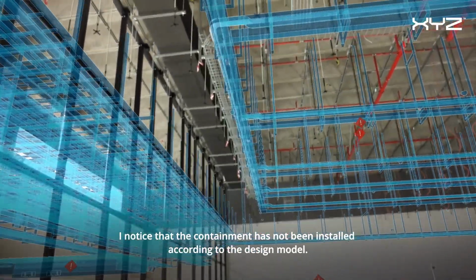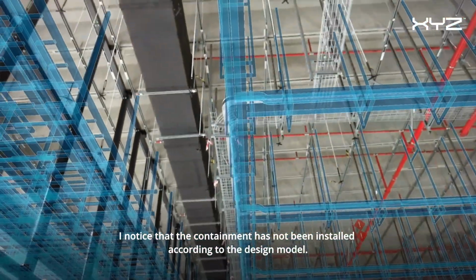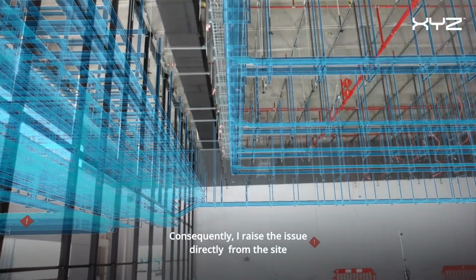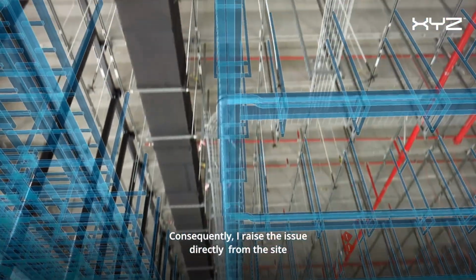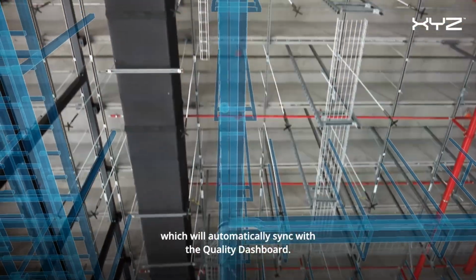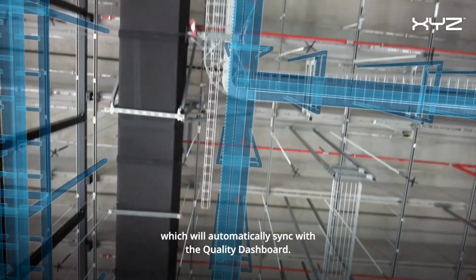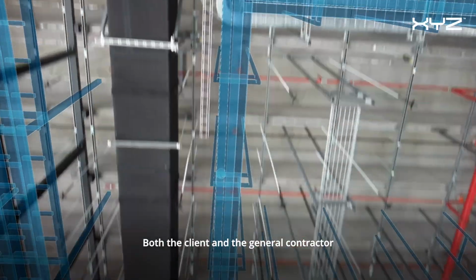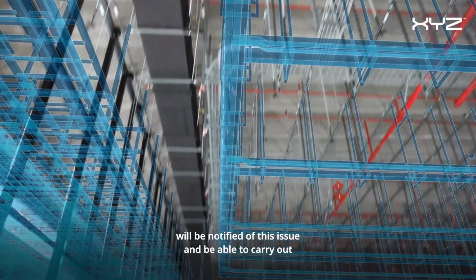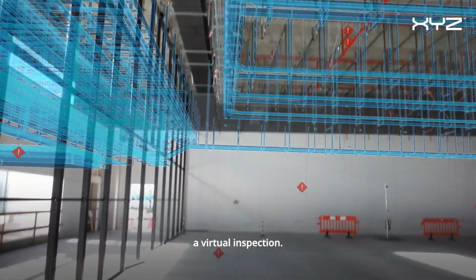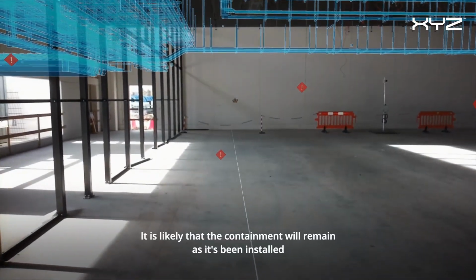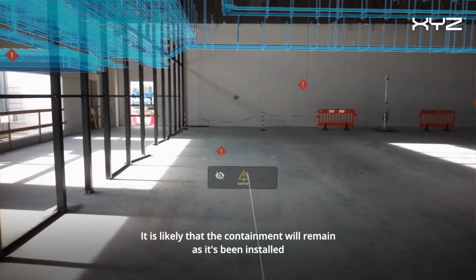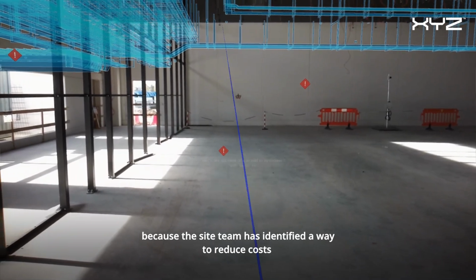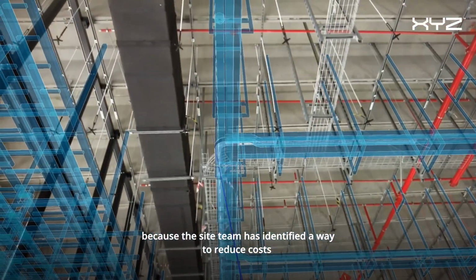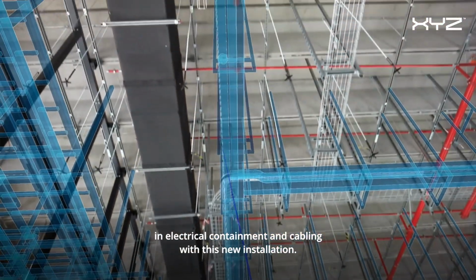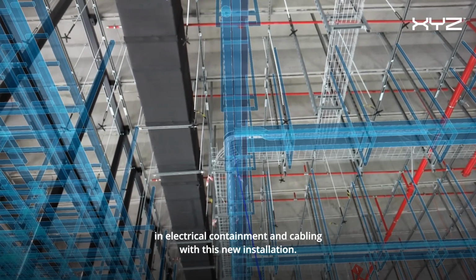I noticed that the containment has not been installed according to the design model. Consequently, I raised the issue directly from the site, which will automatically sync with the quality dashboard. Both the client and the general contractor will be notified of this issue and be able to carry out a virtual inspection. It is likely that the containment will remain as it's been installed, because the site team has identified a way to reduce costs in electrical containment and cabling with this new installation.